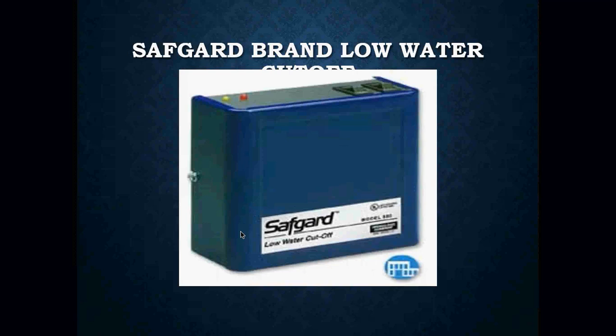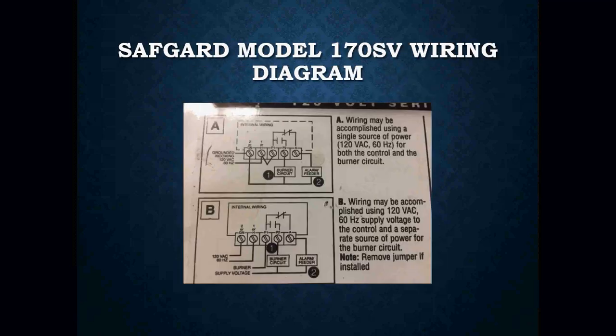This is a Safgard brand low water cutoff — the model 170SV wiring diagram. There are two types of wiring: Wiring A may be accomplished using a single source of power — 120 volts — for both the control and your burner circuit. Your ground and 120-volt power source is wired into your H, then a little jumper between H and P1 sends that out to your controls. P1 and P2 will close to turn on your burner circuit, and the normally closed will open your alarm or feeder in the event of a low water situation.